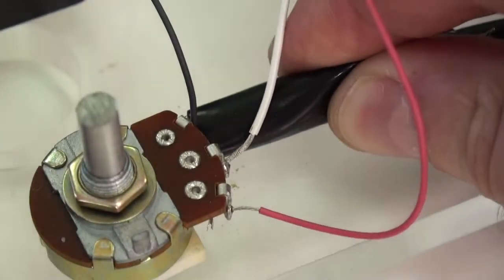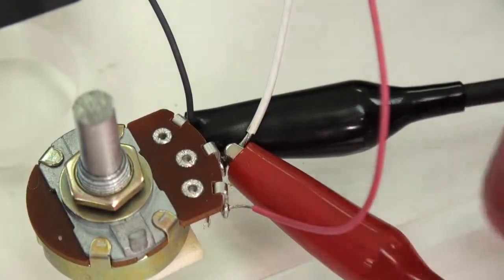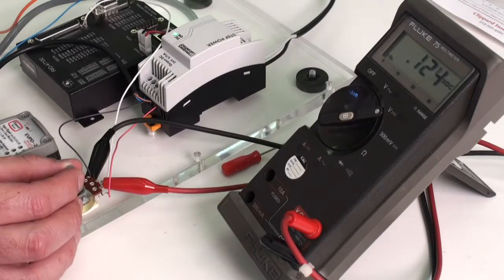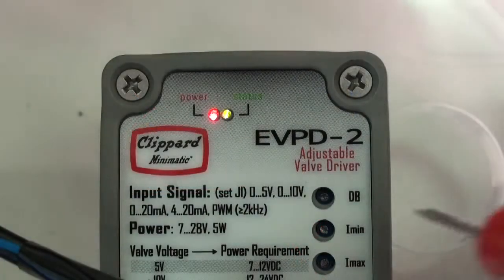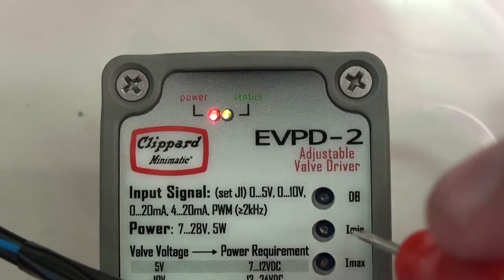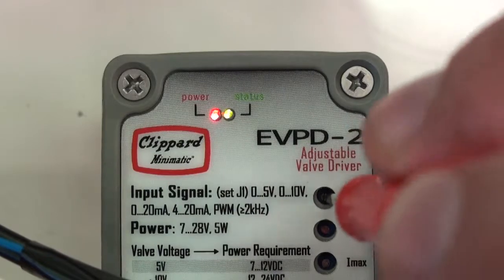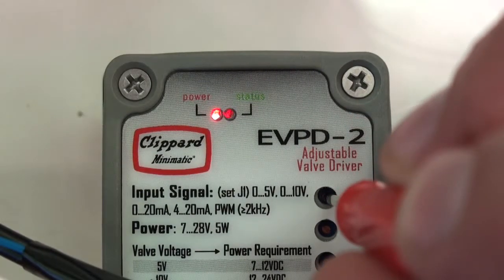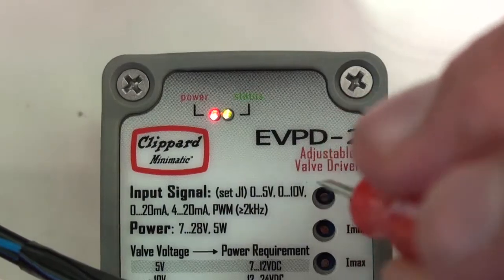So the first thing I want to do is to adjust the command voltage to the minimum voltage for which I'd like to see an output. In this case, let's say 0.1 volts. Now, I adjust the top potentiometer, labeled DB for deadband, clockwise, raising the command threshold until the green status indicator goes dark, at which point the threshold is higher than the signal that I am giving the driver. Then I will turn the pot counterclockwise just enough to get the status indicator to come back on, so we can move to the next step.